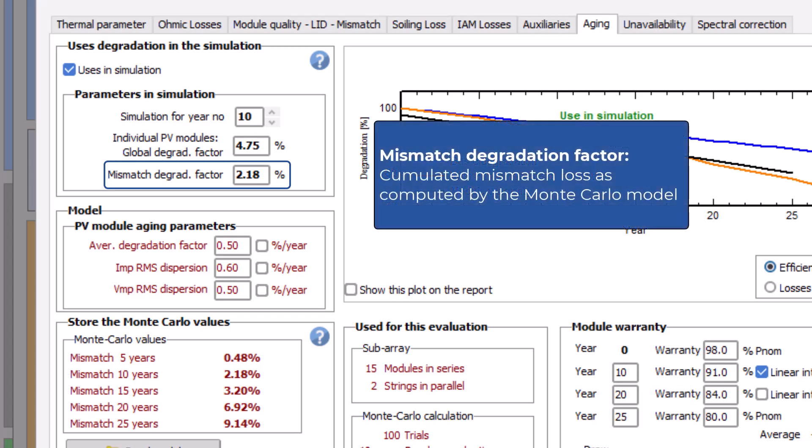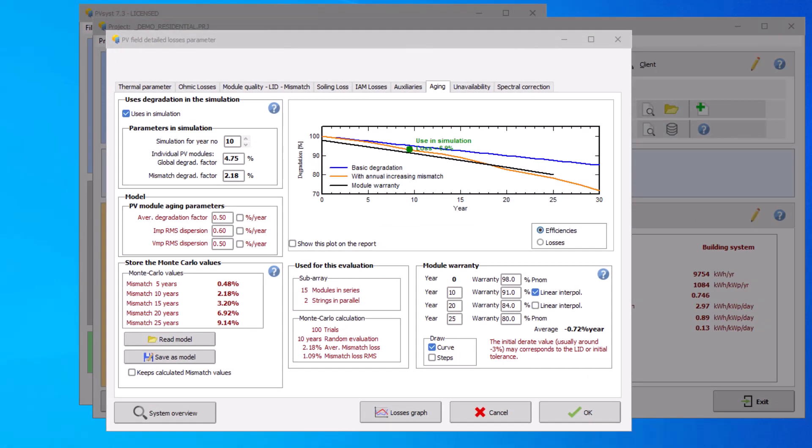The mismatch degradation factor is the cumulative mismatch loss as computed by the Monte Carlo model. The Monte Carlo method is a procedure that uses randomly generated numbers to solve a problem. In our case, this means that PVSYST will generate a series of randomly aged PV modules, assemble them to strings and calculate the resulting mismatch loss. Repeating this a number of times yields an average mismatch loss, which is displayed in the group Monte Carlo values.